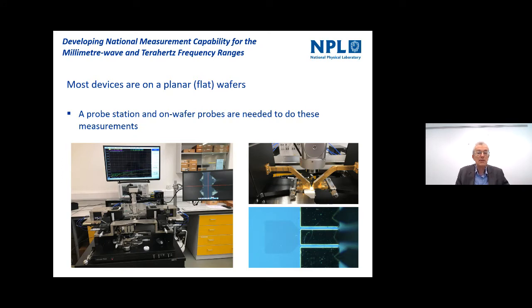In the background is the network analyzer with display unit. There are also 2 extender heads, and then the probe positioners are right in the middle of the photo. And then on the right hand side, the top right hand picture is a close-up showing the probes, which are going from rectangular waveguide down to probe tips, which are coplanar waveguide, where you have a ground and a signal and a ground line. And in fact, in the bottom right, you can see those probes landing onto a coplanar waveguide, which on this occasion has, it's difficult to see, but there's an on-chip graphene antenna which is sticking out of the coplanar waveguide line. So here we're able to characterize that antenna on wafer using the probes that take us from the wafer back through the extender heads in waveguide and then right the way back to the network analyzer. So again, now the network analyzer is enabled to do measurements like antennas on planar circuits.